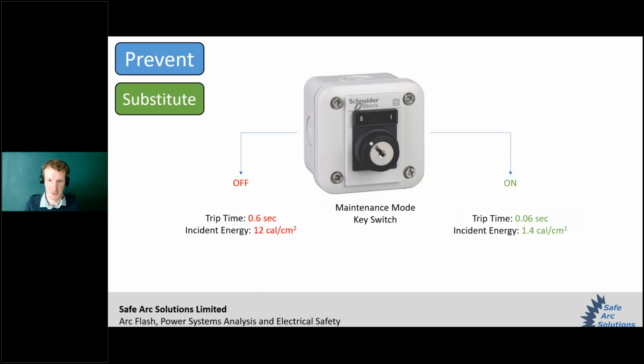This is within the substitution category from the hierarchy of risk controls. It's something called a maintenance mode key switch. It's quite a popular mitigation measure. Basically, you're temporarily going to make your overcurrent protection more sensitive to a trip. So if an arc flash does occur, the protection is going to recognize that very, very quickly, trip the circuit breaker, and therefore keep your incident energy down as much as possible.